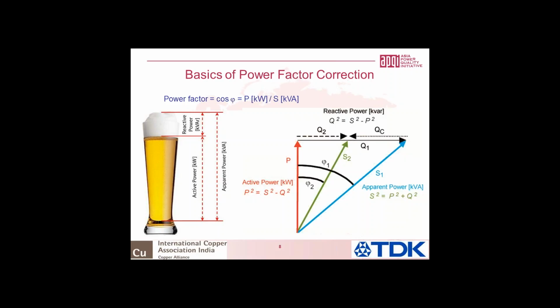that you've got a larger portion of the glass which is filled with froth, which is occupying the space, but you're not keen on paying for it. To the right, you would see the classical phasor diagram, where you have the real power. You have two apparent powers depending on the phase angle. And what you see, QC, is a capacitive VAR which we're going to inject to reduce the total reactive VAR, by which the reactive VAR comes down and the phasor angle from phi1 becomes phi2.